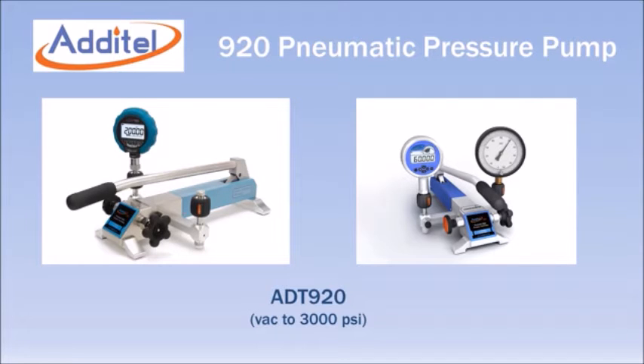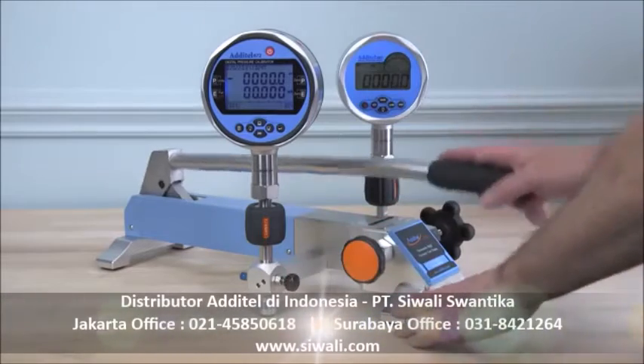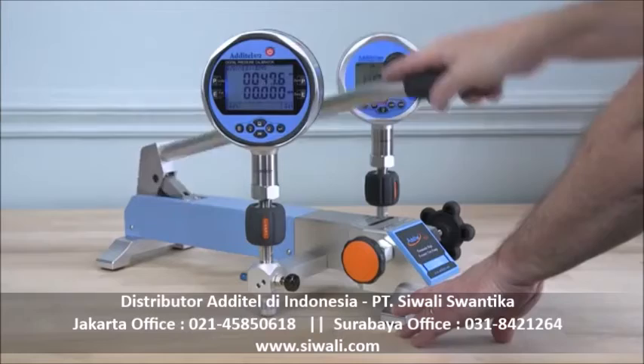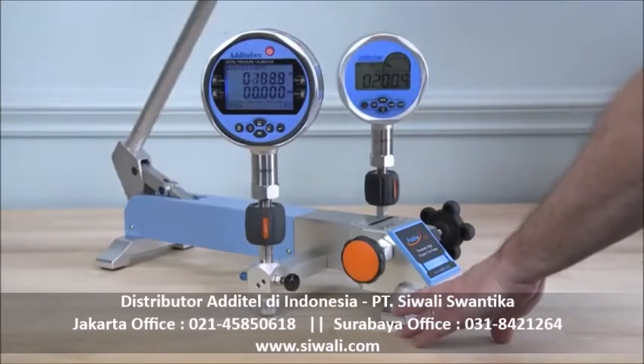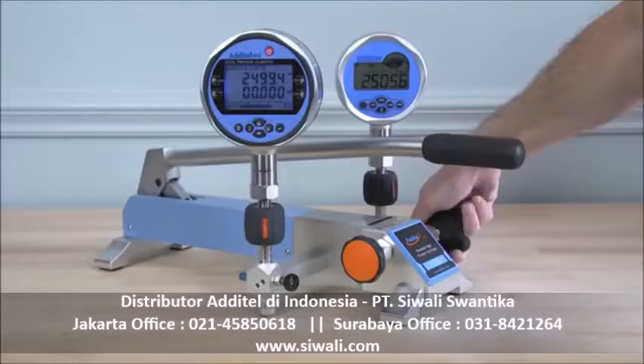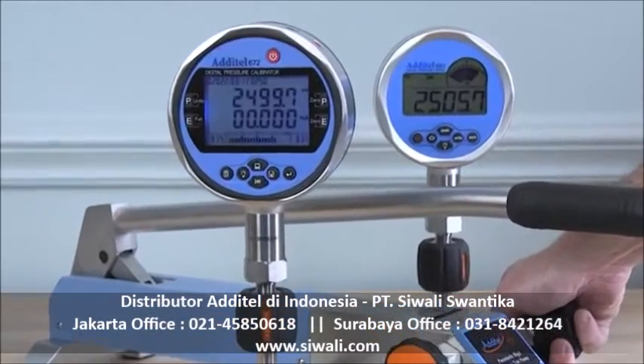The Additel ADT920 is a truly unique pneumatic pressure pump with a maximum range of 3,000 PSI. The long handle allows rapid pressure generation to 3,000 PSI in only 40 seconds, while a high-quality screw press gives fine adjustment resolution as low as 1,000th of a PSI. No one else in the marketplace offers a product with these features.